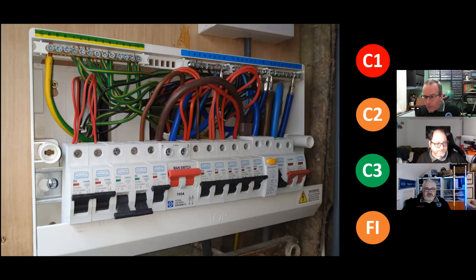My heart is telling me C3, but again with the RCD, and the RCD must push it to the C2 if the RCD is needed. The other thing here is that the RCD on the right is an 80 amp, I believe. And if you look at the actual circuit breakers it's supplying, you've got three 32s, a 40 and a 16.